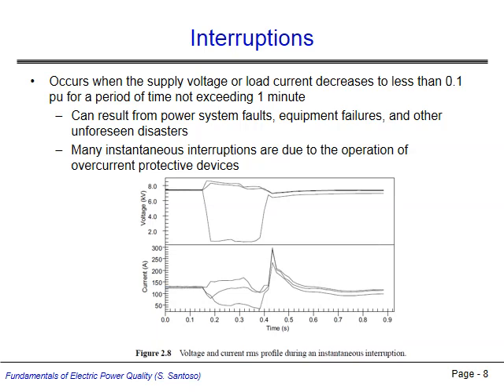Voltage interruptions occur when the RMS voltage magnitude falls to less than 10% of its nominal value. There are many possible causes of interruptions, such as faults on the power system or equipment failures. Most often, however, interruptions occur as a result of an overcurrent protective device operating. For example, if a circuit breaker is called upon to isolate a short circuit fault on the system, the opening of the circuit breaker will isolate any downstream customers from the power source, driving their voltage to zero while the breaker remains open. The figure shows an interruption occurring on one phase, lasting for about 0.2 seconds. Notice that the other two phases experience voltage swells during the event.